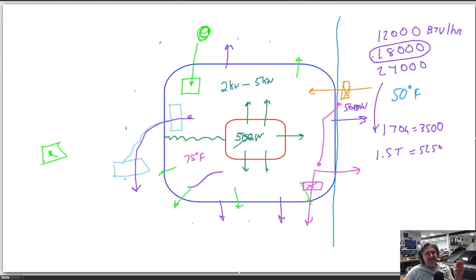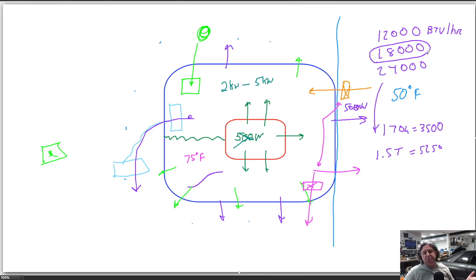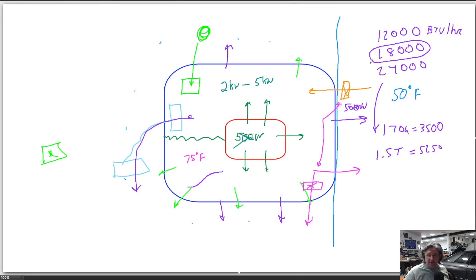The capacity also depends on humidity because it takes energy to remove moisture from air — roughly 970 BTUs per pound of water. If the room is very humid, a lot of the BTU capacity gets used just removing humidity without lowering the temperature at all. Nonetheless, an 18,000 BTU mini split — what I have — is about 5,000 watts on the high side.